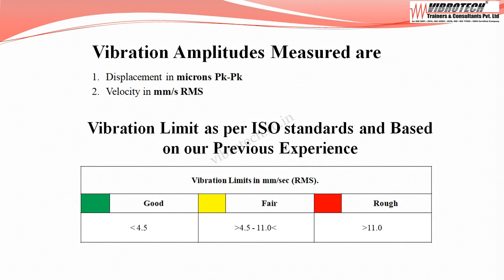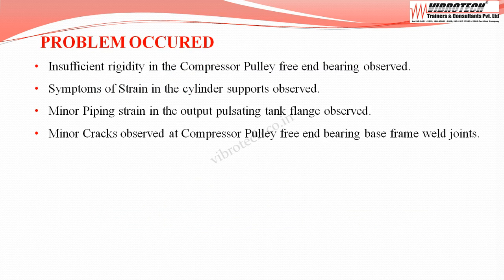Now onto the vibration limits. As per ISO standard and with previous experience: when the velocity falls below 4.50 mm/s rms, it is considered good. When the velocity falls between 4.50 to 11.0 mm/s rms, it is considered fair. When the velocity falls above 11.0 mm/s rms, it is considered rough.